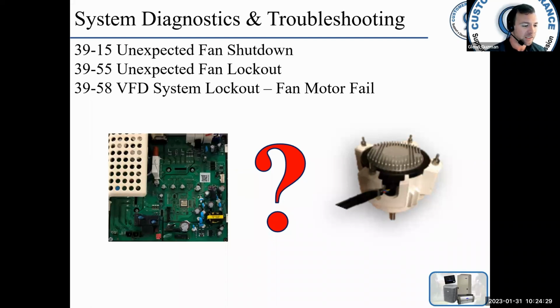In rare cases, you've replaced the motor, then the VFD, but sometimes you can get away with looking at what other faults are occurring. And like I told you before, there's other faults that could be occurring or will occur with this. And if we can try to eliminate some things as we go along, we might find out, hey, this is just the VFD or it's just the motor and not both.